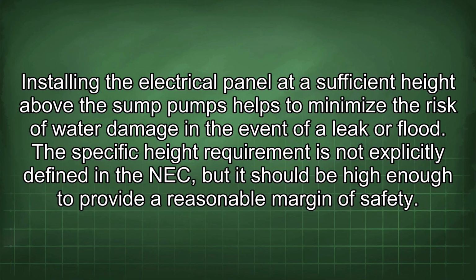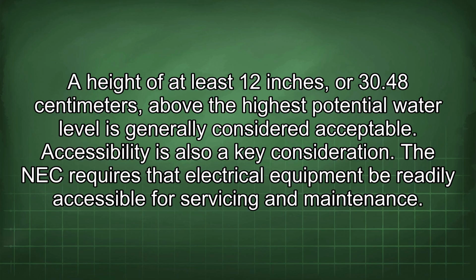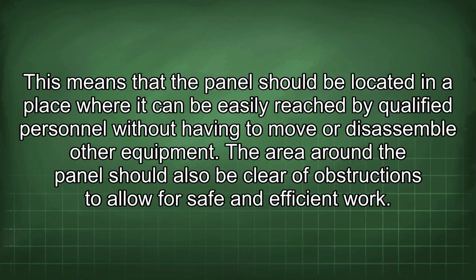The specific height requirement is not explicitly defined in the NEC, but it should be high enough to provide a reasonable margin of safety. A height of at least 12 inches, or 30.48 centimeters, above the highest potential water level is generally considered acceptable. Accessibility is also a key consideration. The NEC requires that electrical equipment be readily accessible for servicing and maintenance. This means that the panel should be located in a place where it can be easily reached by qualified personnel without having to move or disassemble other equipment. The area around the panel should also be clear of obstructions to allow for safe and efficient work.